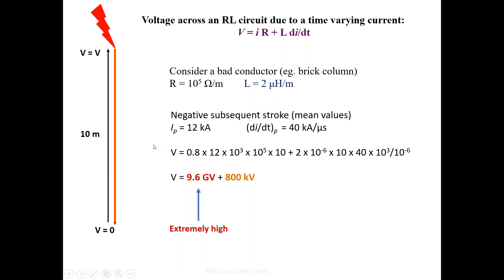And then if I apply these values into the above equation, we get this. There will be an enormous voltage, 9.6 gigavolts, due to the resistive component, and a rather moderate value compared to the resistive component due to the inductive component, 800 kilovolts, in this 10-meter long structure. Now you will understand that when lightning strikes a bad conductor, such a large voltage is developed. So the result would be sometimes arcing, sometimes explosions, and it can be many hazards.